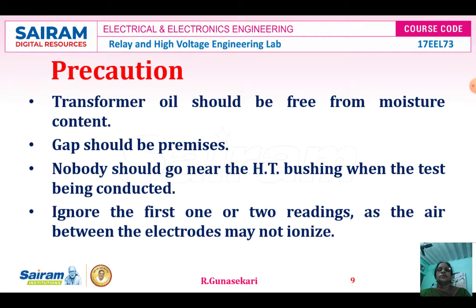Precautions. The transformer oil should be free from moisture content. Nobody should go near the high voltage bushing when the test is being conducted. Ignore the first one or two readings. That means we are taking a minimum of two or three readings. The average value only is considered as the breakdown strength of the transformer oil for the given sample. The air between the electrodes may not ionize.